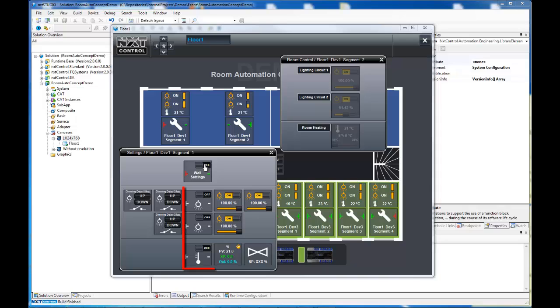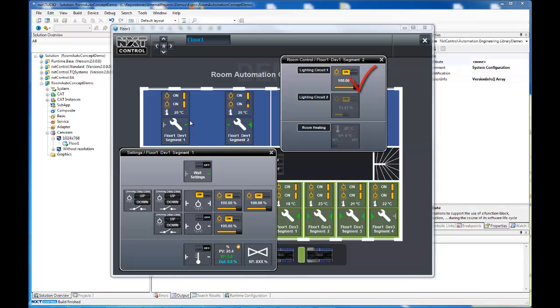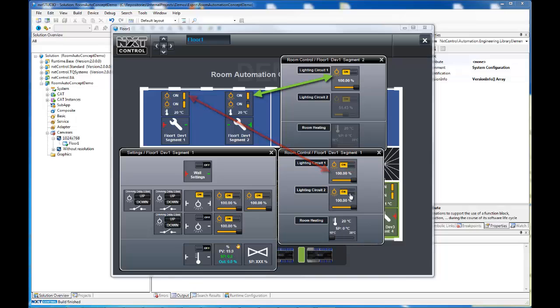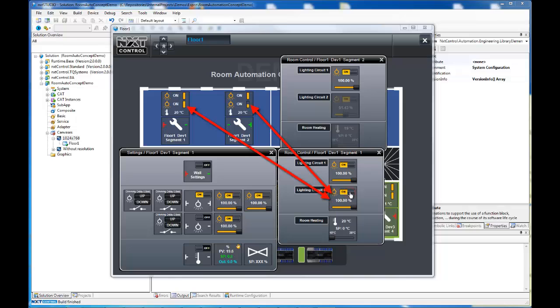At the same time the border settings for each lighting circuit and the room heating are individually controllable. For example, we will set the border just for one lighting circuit again. This circuit is now acting the same way as it did before we removed the wall. The other circuit without the border can now be switched on or dimmed for both segments together, and all this with a few mouse clicks.